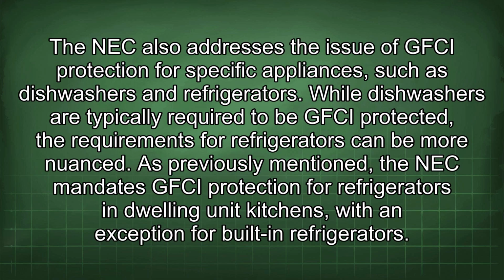The NEC also addresses the issue of GFCI protection for specific appliances, such as dishwashers and refrigerators. While dishwashers are typically required to be GFCI protected, the requirements for refrigerators can be more nuanced. As previously mentioned, the NEC mandates GFCI protection for refrigerators in dwelling unit kitchens, with an exception for built-in refrigerators.